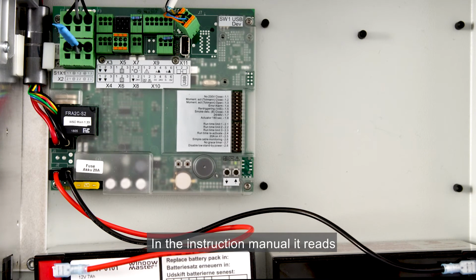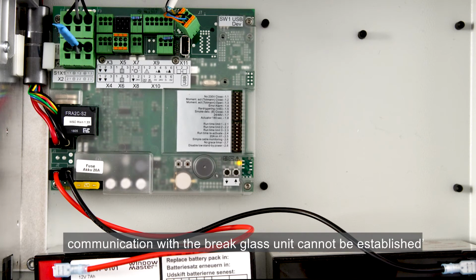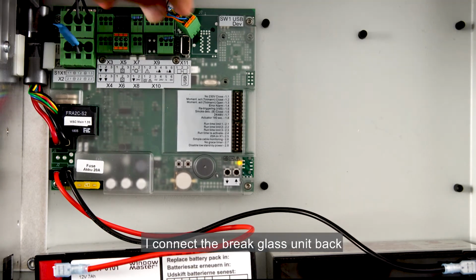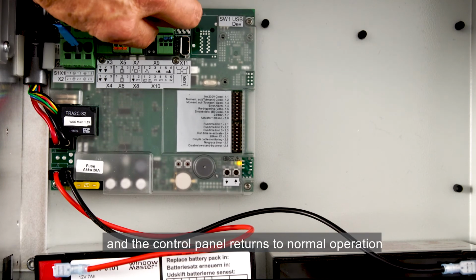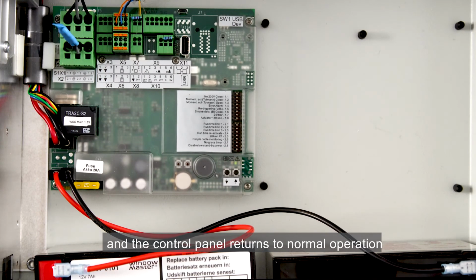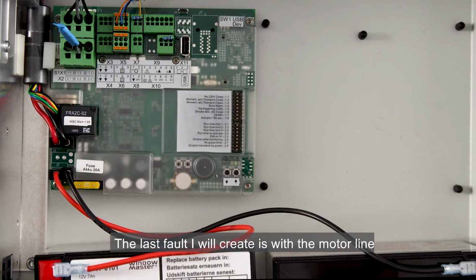In the instruction manual it reads, problem on X5, X6 break glass unit. Communication with the break glass unit cannot be established. I connect the break glass unit back and the control panel returns to normal operation. The last fault I will create is with the motor line.